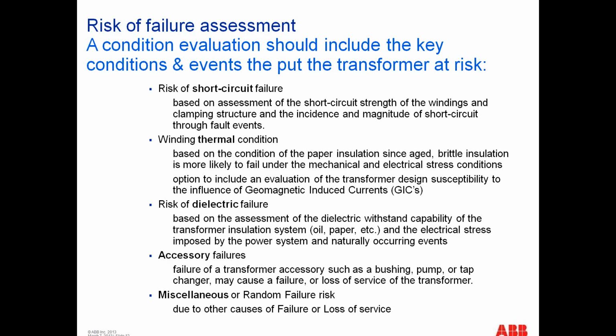And that heat, unfortunately, for the organic materials and some of the polymeric materials in the transformer actually contributes to their end of life. It causes breakdown to occur. And so if the thermal condition of the transformer isn't so good, if you've got a cooling system that's not quite up to where it should be, there's going to be problems with that transformer. And of course, the dielectric failure is another point of risk where the transformer can be damaged from lightning strikes, switching surges, other dielectric events occurring on the system.